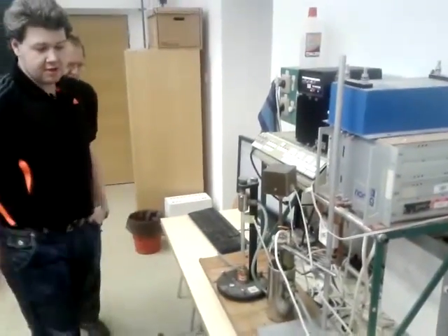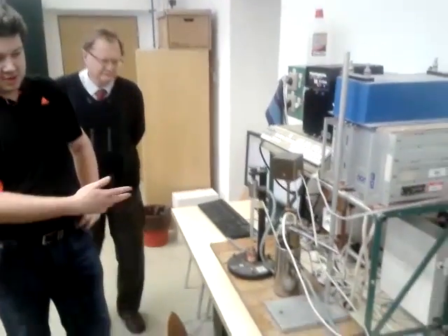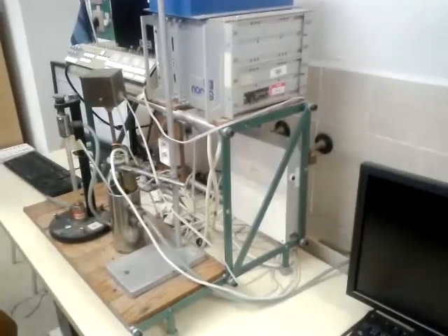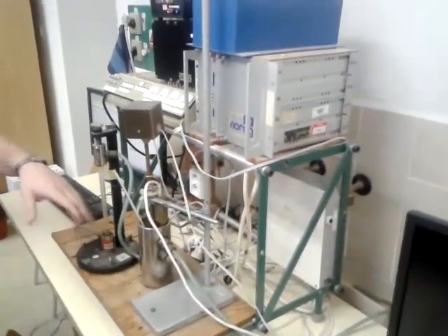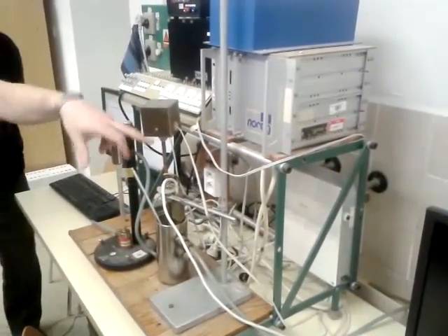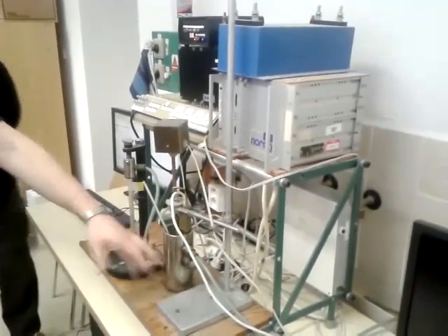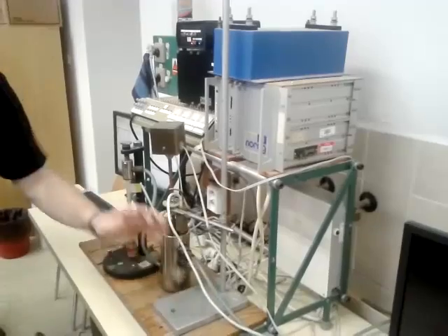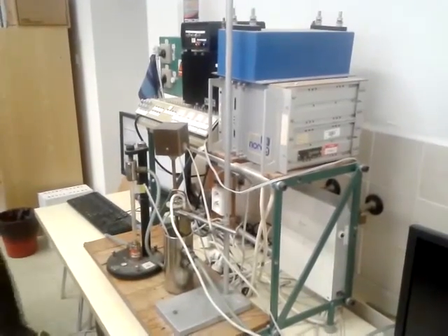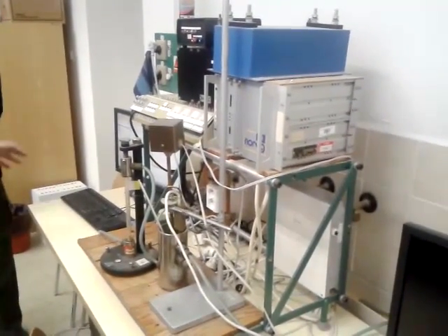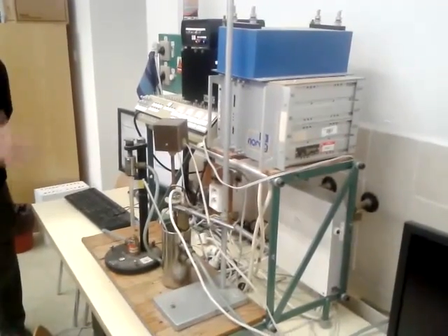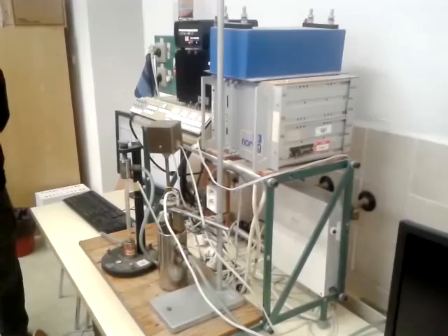In the boiler, down at the bottom, is a heating spiral, and the power on the heating spiral is controlled by an external power source. The temperature of the water is measured again by a PT100 sensor, on the level or water flowing out from the heater. And the flow rate through the heater can be constant or controlled.